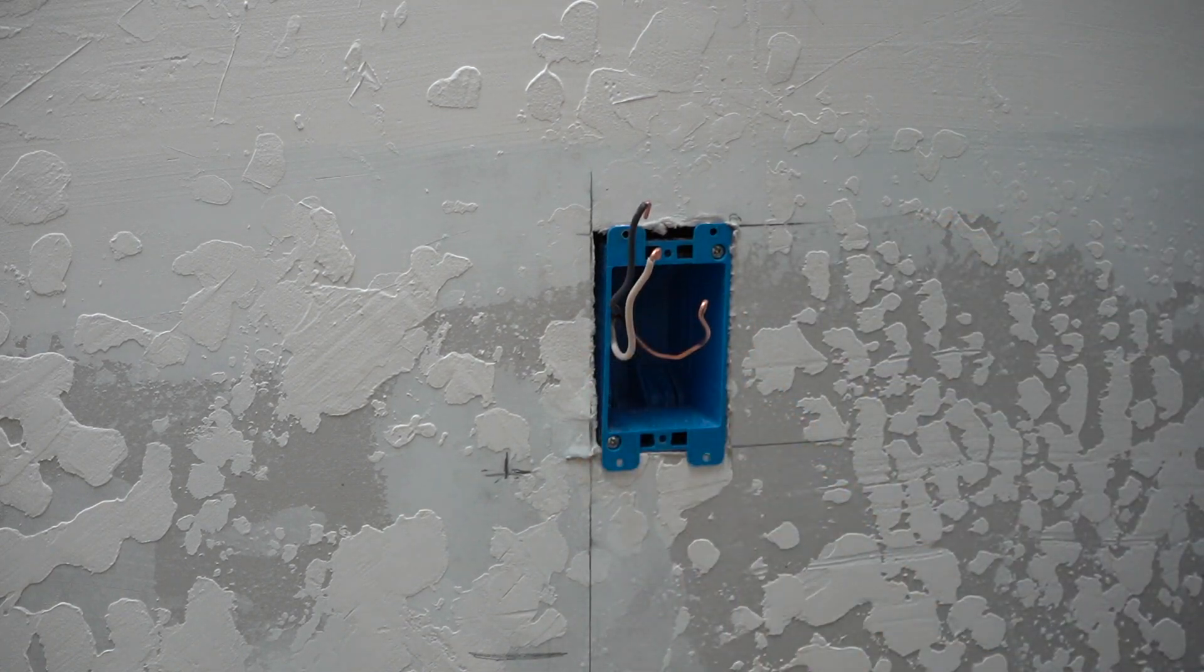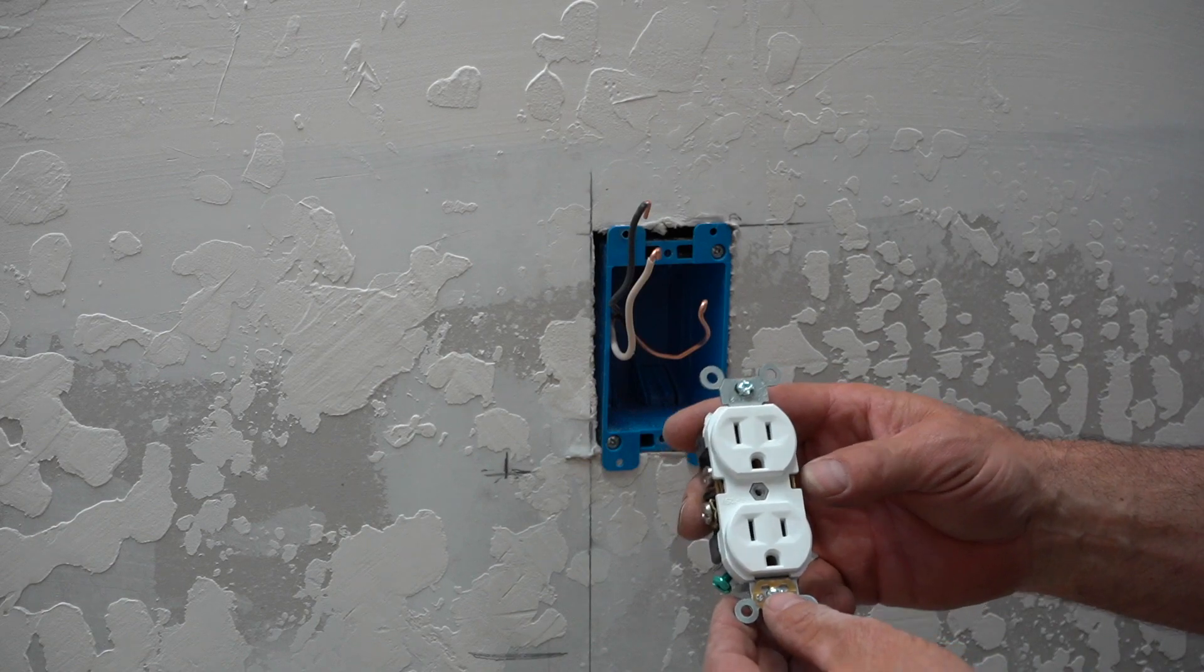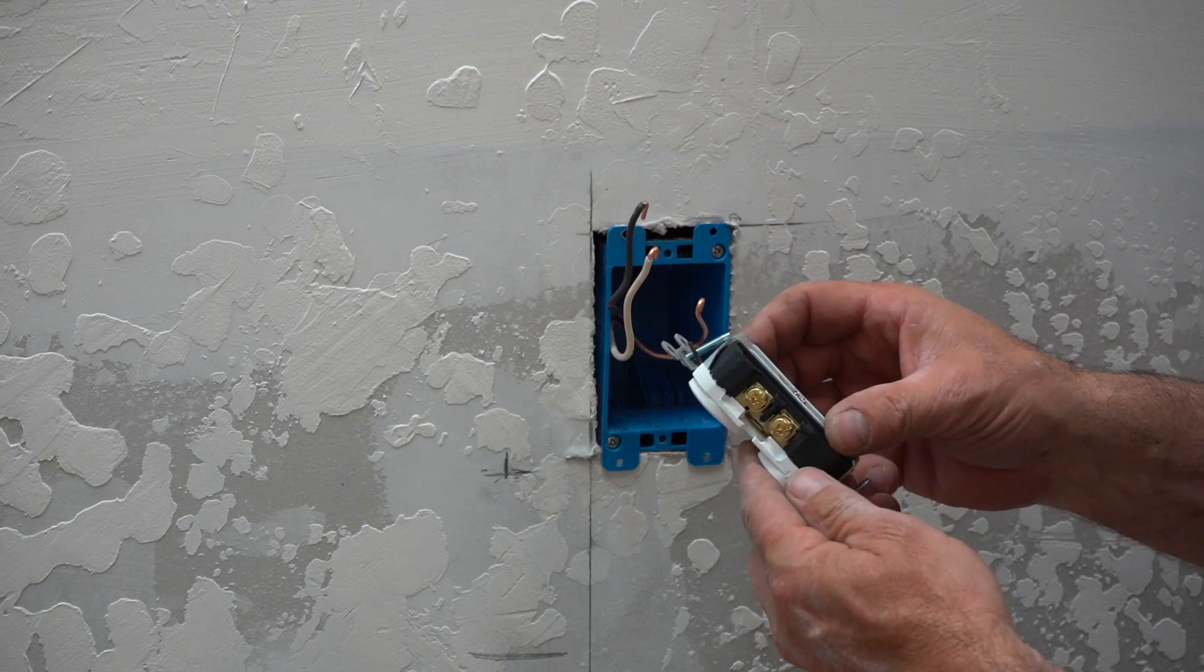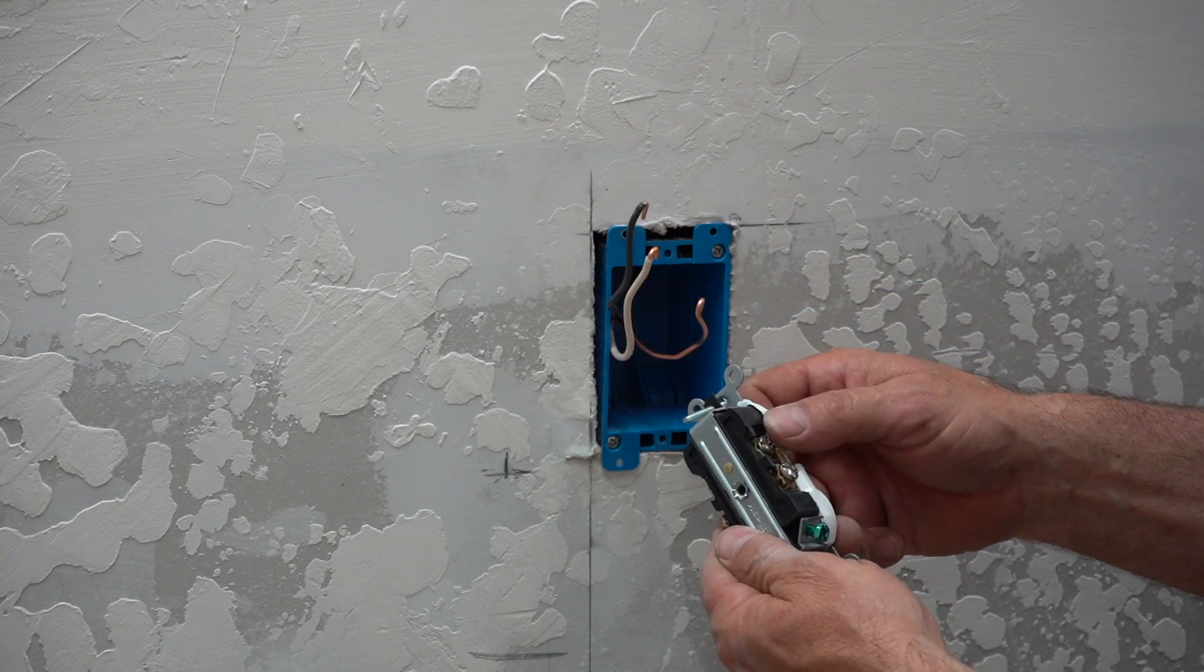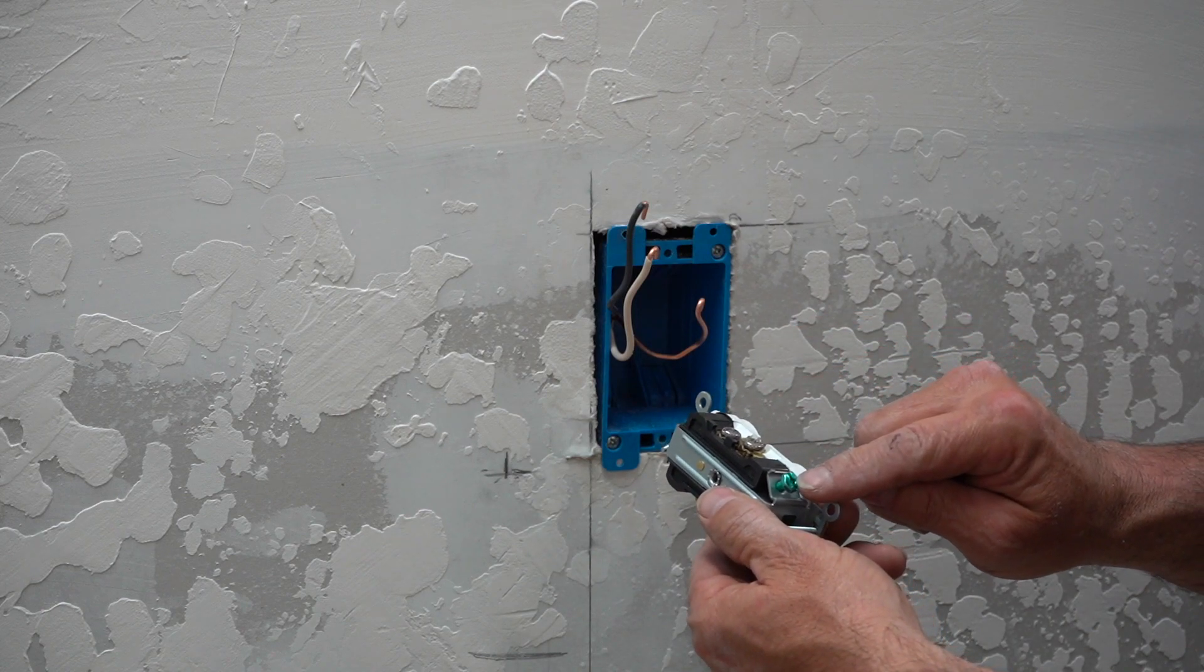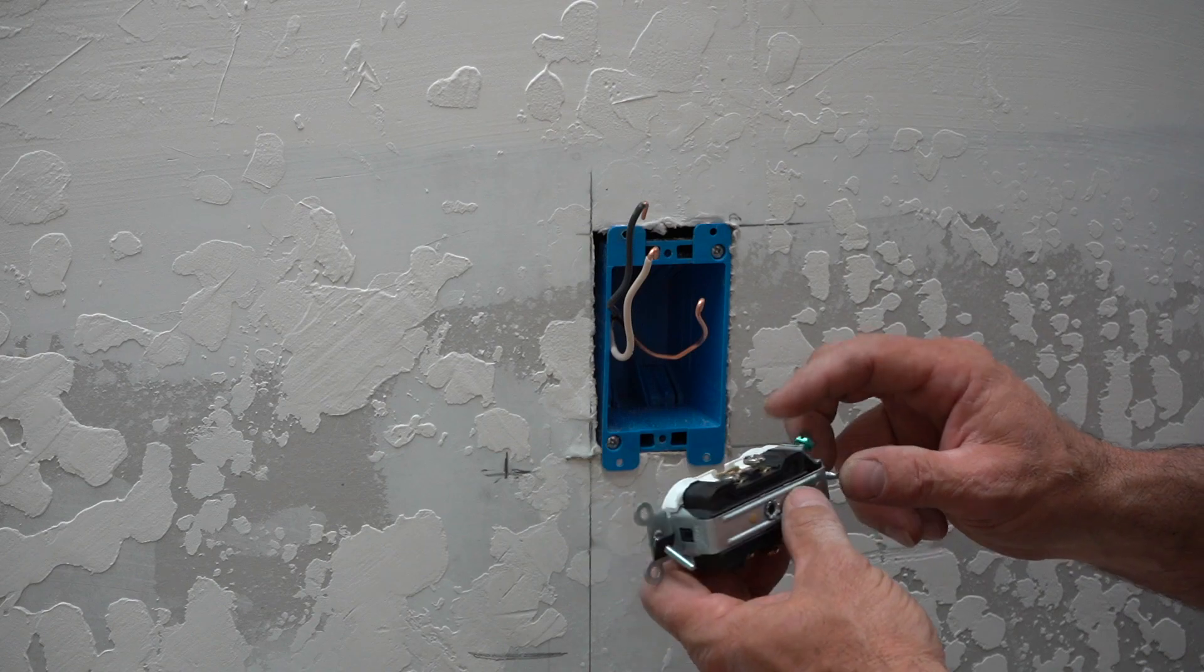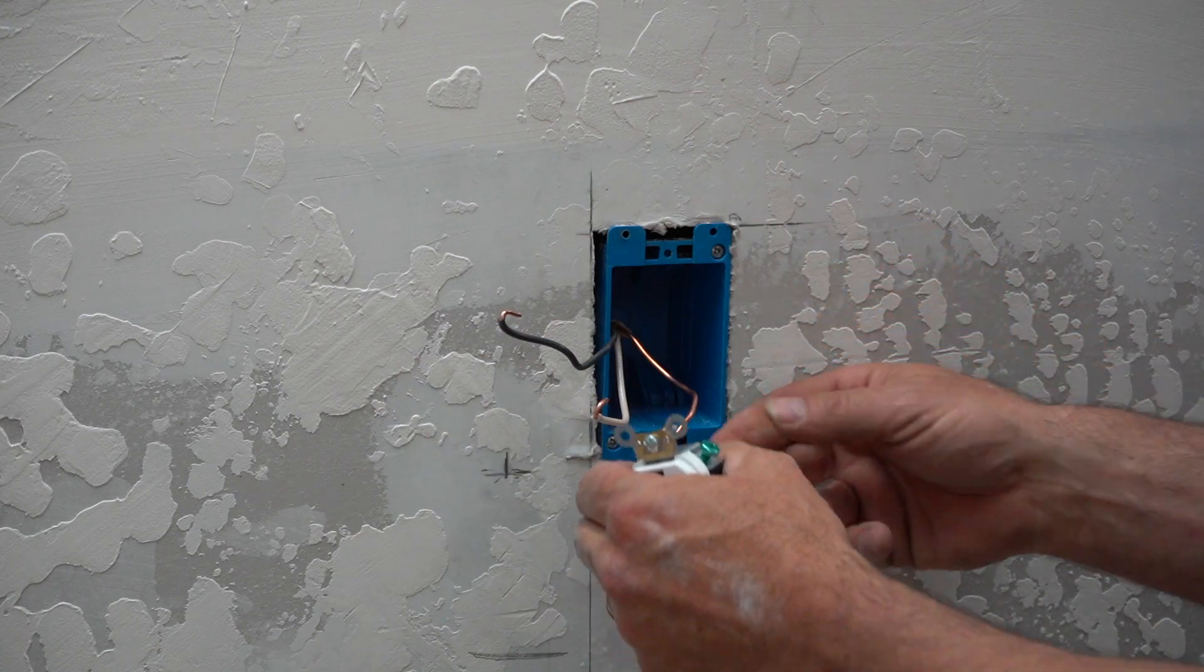Okay, now when you get the new receptacle you're gonna put it with the ground down. We have a hot which is gold, and then we have the common which is silver. Common and the ground are on the same side. We're going to go ahead and install the ground first.